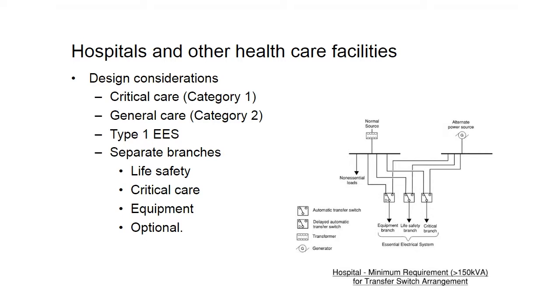And then oftentimes you'll see optional loads as well. So these are loads that are not required by code, but something that the facility or the hospital would want to see on emergency power backed up. These might be loads like cooling or chilling loads, chiller loads. Oftentimes maybe you'll see refrigerators or freezers in a dietary area to preserve the food if there's a prolonged outage. So those things that are not required by code would fall under the optional load category.